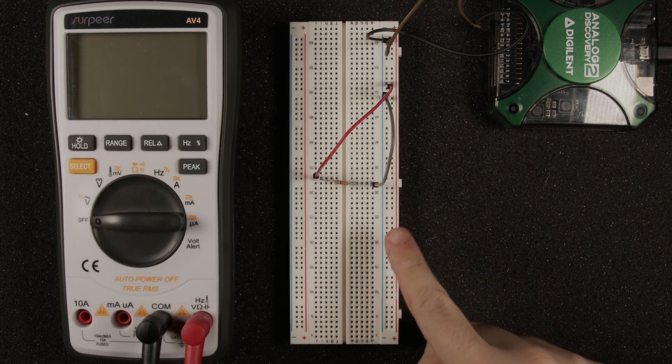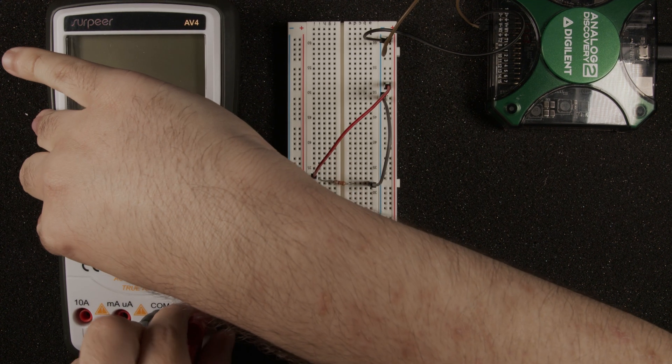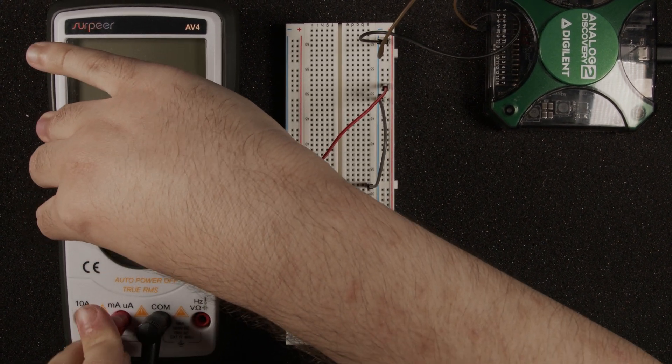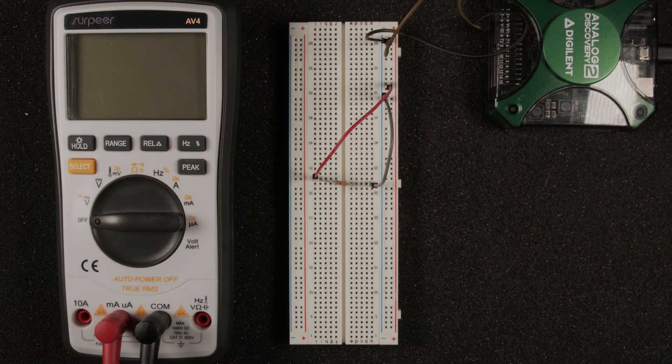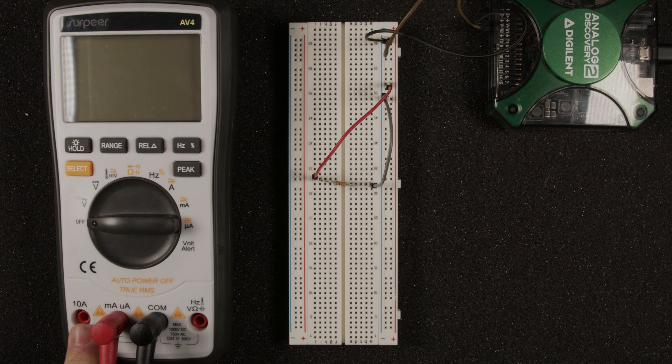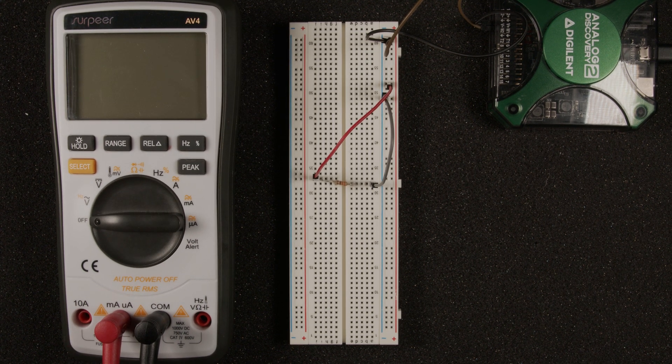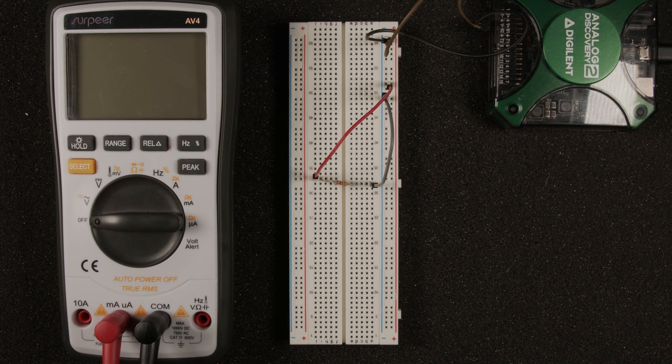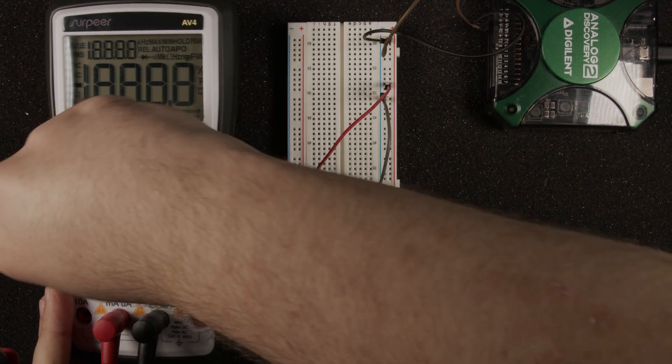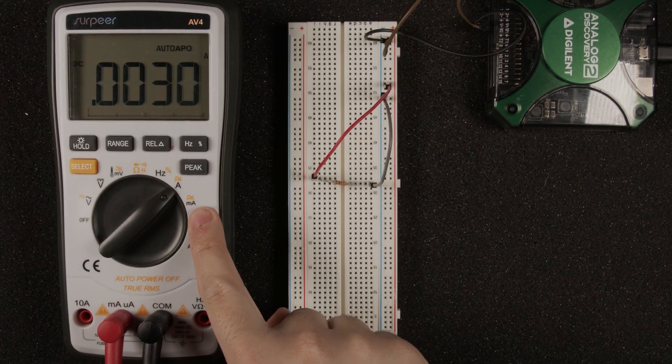So for me, I know that this is going to be in the milliamp range, so I am going to unplug it from voltage and plug it into milliamps. If you are not sure what range you're going to be in, it is always best practice to start with the highest fused one and then work your way down. Since I am measuring milliamps, I am going to turn my dial to select the milliamp range here.